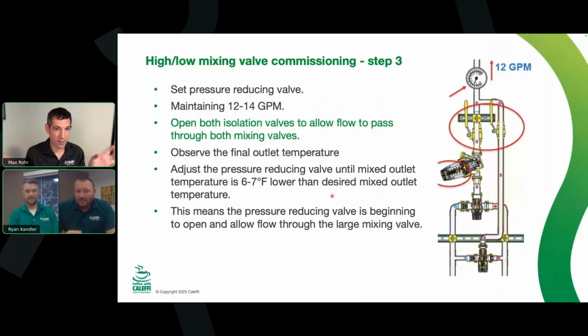Then we have this for big and small, but now tell us how we merge that so it all makes sense. Yeah, so then you just want to keep that flow up there at 12 to 14 GPM, keep your eye on that gauge, and adjust that PRV and get it set to 6 to 7 degrees lower than your set point. For example, you're going to be looking for 113, 114 coming out. That's going to give you the coverage for both of those scenarios.